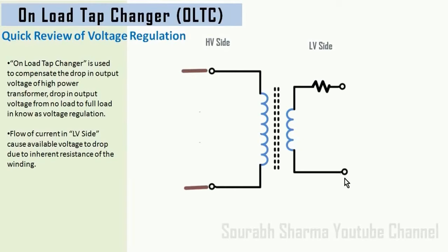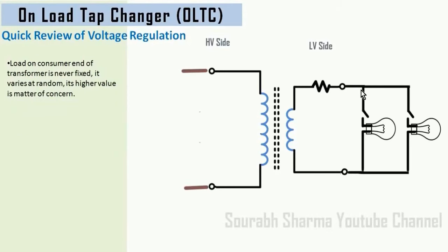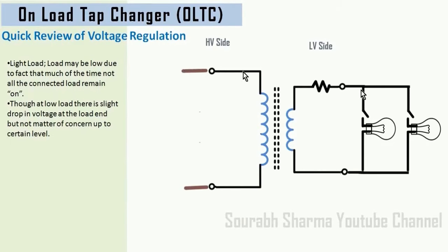Suppose we have a distribution transformer at the load end, so it must be a step-down transformer, and a number of loads are connected to the secondary winding. This represents the internal impedance of the secondary winding. When the transformer is on no-load — that means all connected loads are off — however the transformer is in working condition, meaning it is energized from the HV side. In this condition, the output voltage will be exactly equal to the voltage induced in the secondary winding, because no current is flowing; therefore, whatever be the impedance of the secondary winding, no voltage will drop.